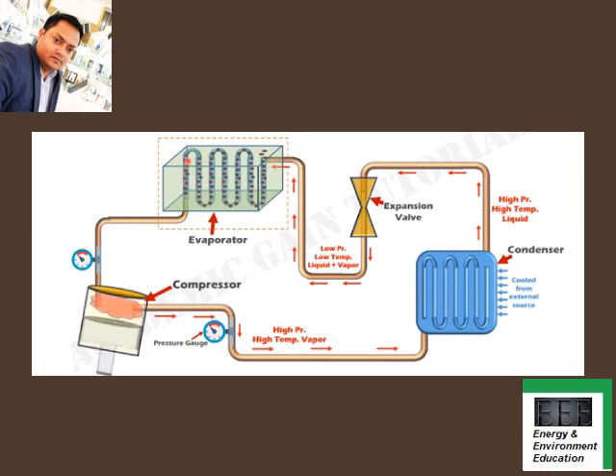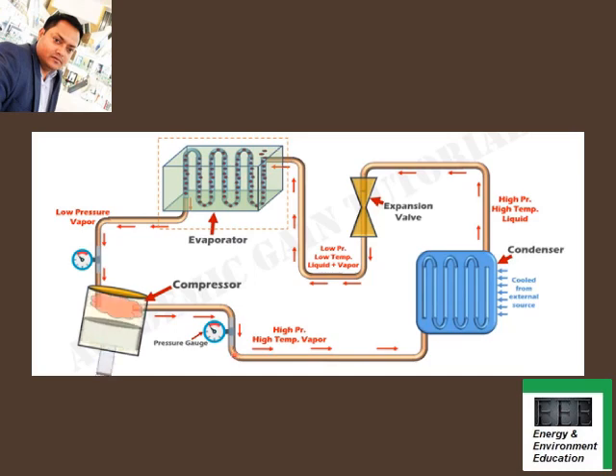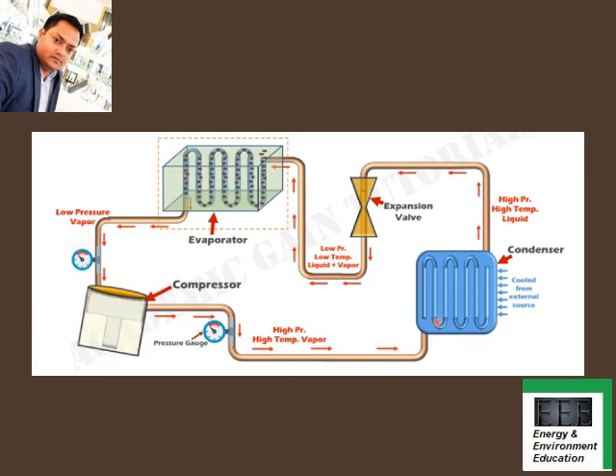This cold liquid and vapor mixed refrigerant is then passed to the evaporator, where the main cooling effect occurs. The low-pressure, very cold liquid refrigerant enters the evaporator coils, absorbs all the heat from the surrounding region, and completely turns into low-pressure vapor refrigerant inside the coils. The surrounding region becomes cold by losing heat, achieving the refrigeration effect. This low-pressure vapor then leaves the evaporator and re-enters the compressor, and the cycle repeats continuously to provide continuous cooling.